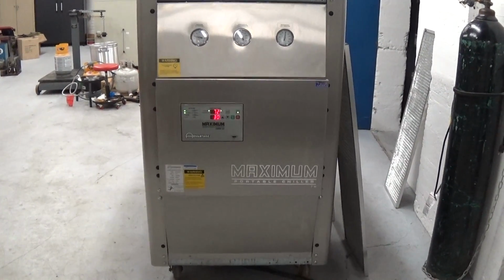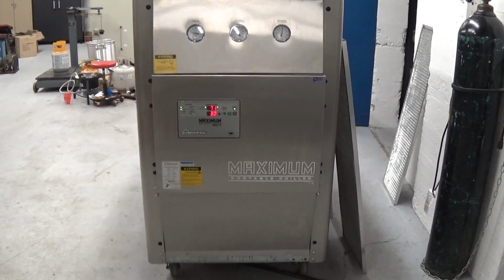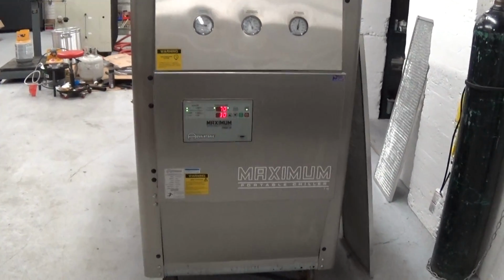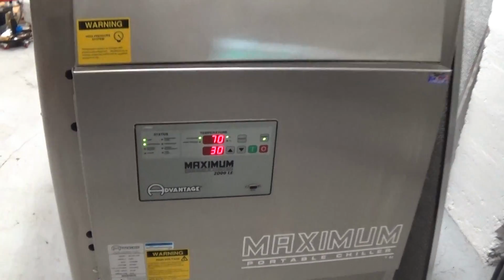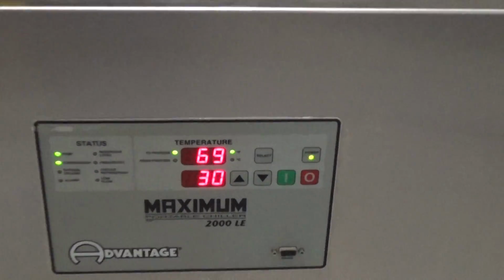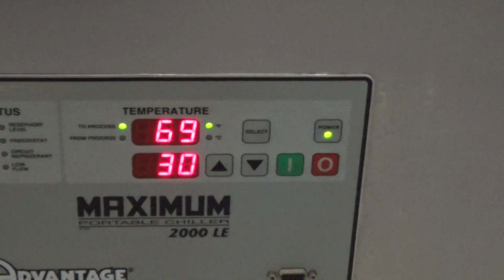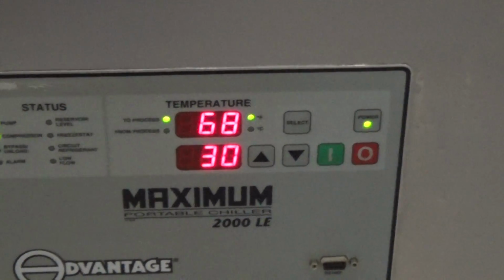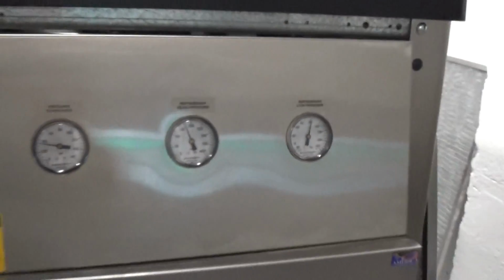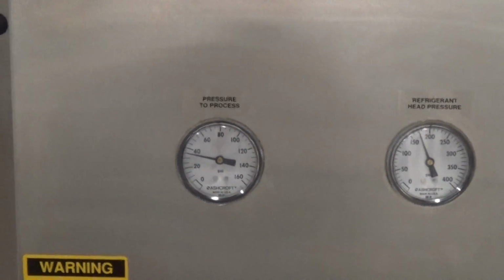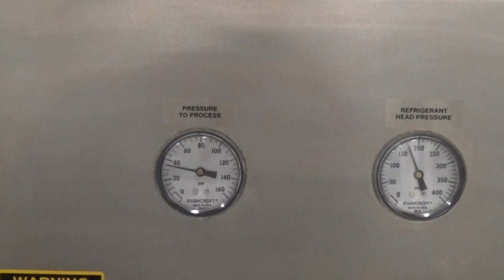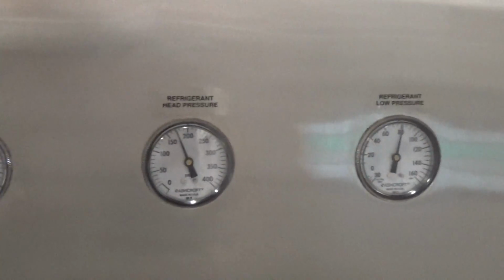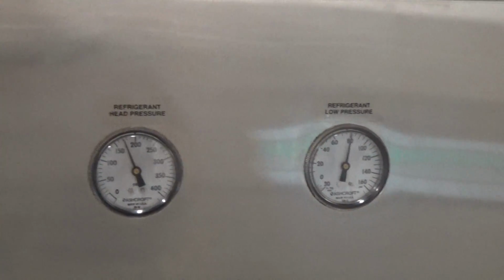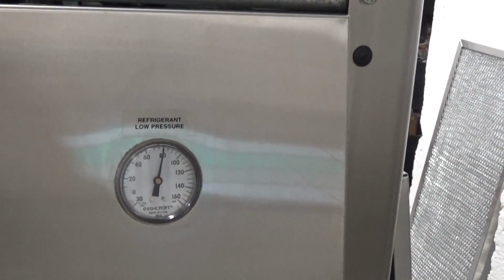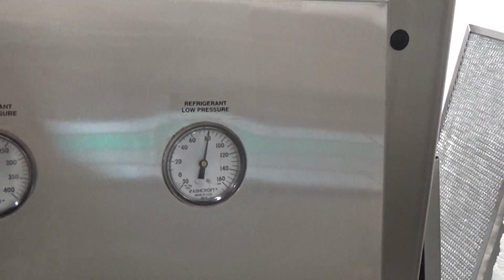Our video number 2 for this 10-ton air-cooled Advantage chiller set up for a brewery. The compressor and the fan just kicked on, so we're starting to cool. It will cool fairly rapidly because we've got very little load on this unit. We have 3 gauges on the front, all checked out and working fine. Right now it shows our pump pressure just shy of 40 psi.